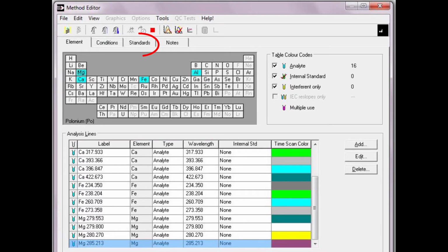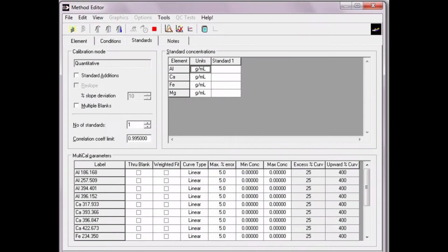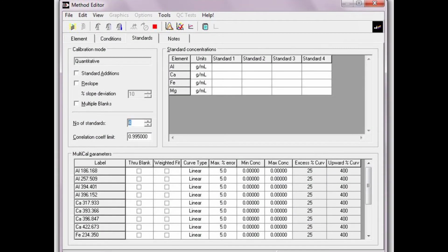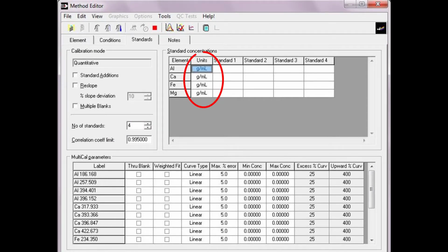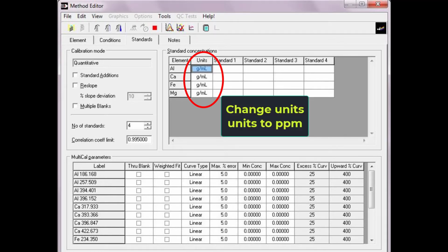Next, select the Standards tab. Next to Number of Standards, input the number of tubes of standards you will be running. Note that this does not include a blank. Under Units, click on grams per mil and select ppm from the pull-down list for each element.